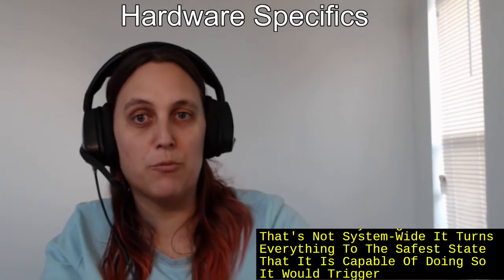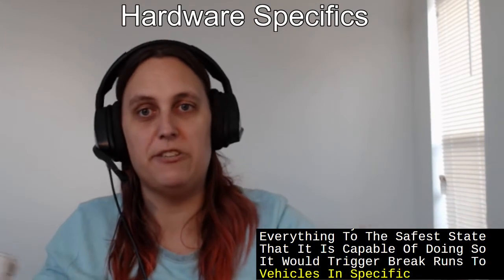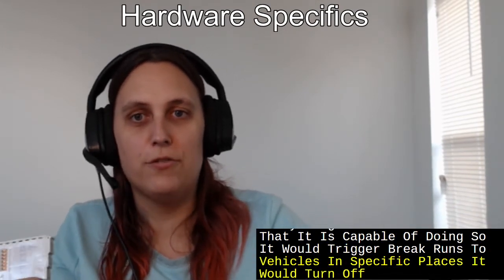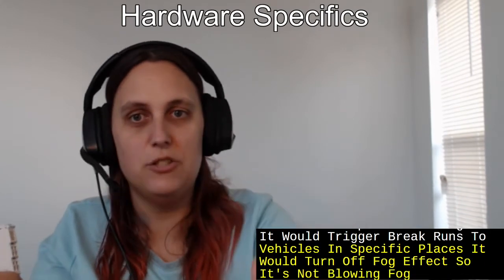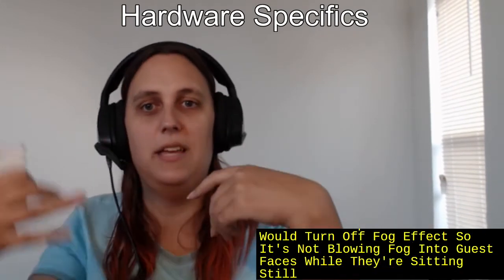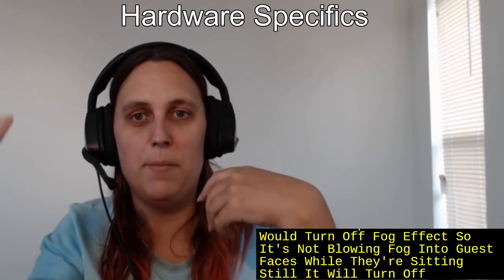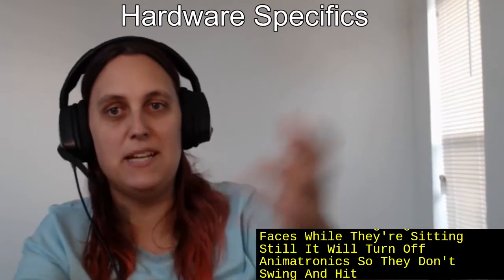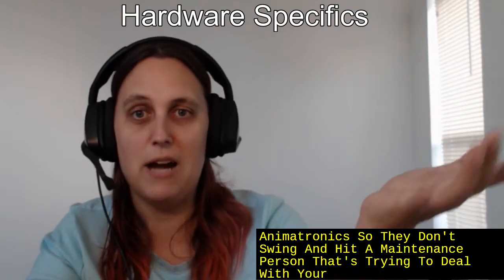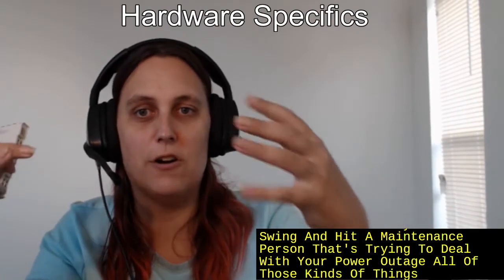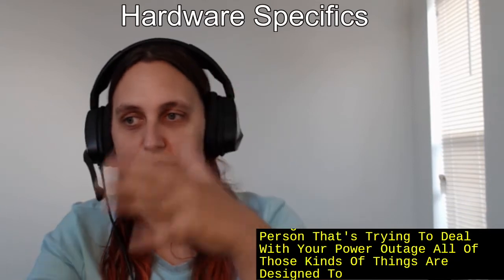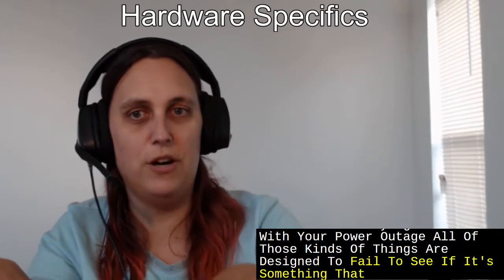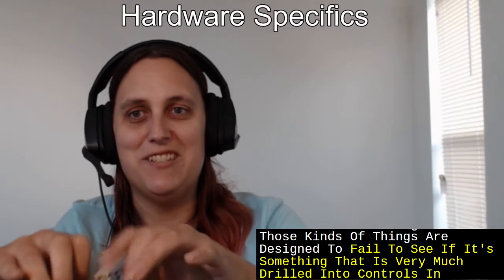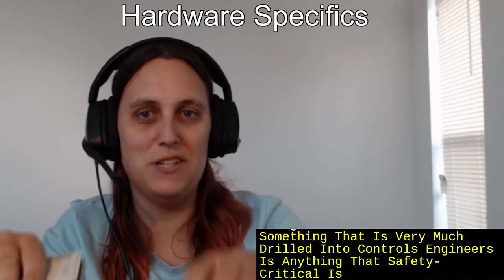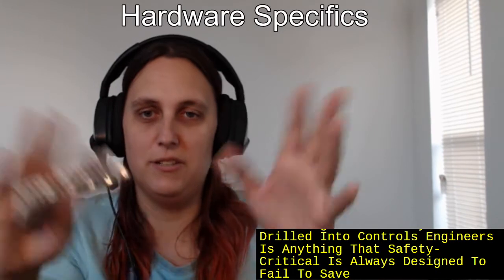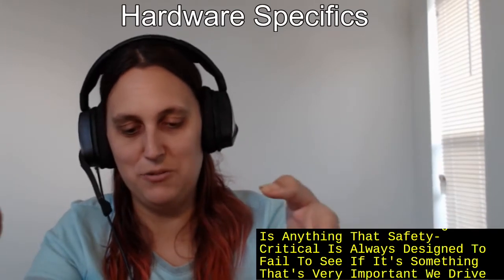So it would trigger brake runs to stop vehicles in specific places. It would turn off fog effects so it's not blowing fog into guests' faces while they're sitting still. It will turn off animatronics so they don't swing and hit a maintenance person that's trying to deal with your power outage. All of those kinds of things are designed to fail to safe. It's something that's very much drilled into controls engineers: anything that's safety critical is always designed to fail to safe. It's something very important that we drive into people.